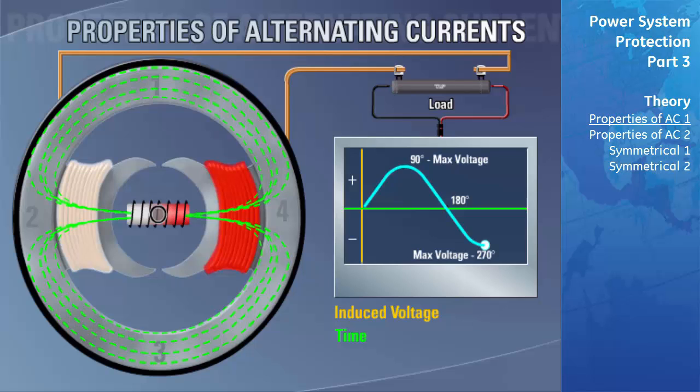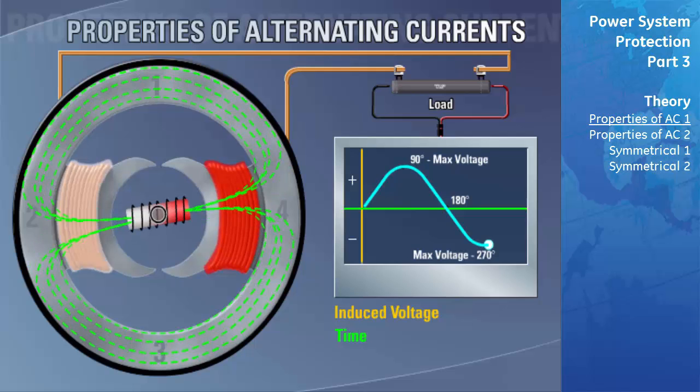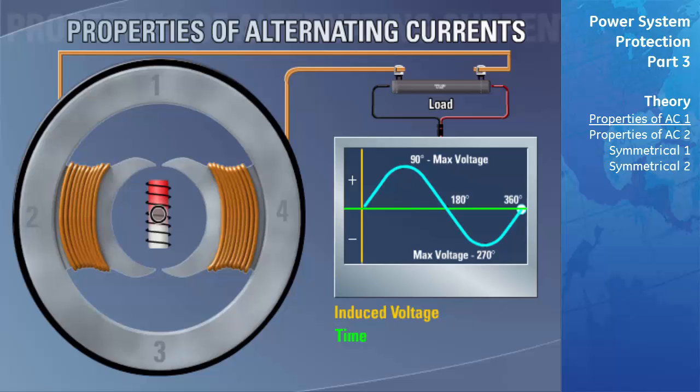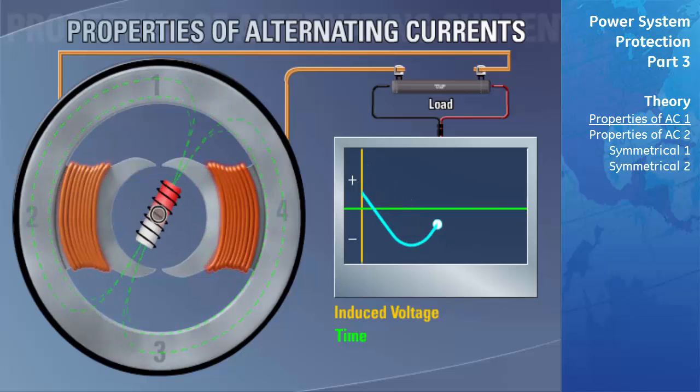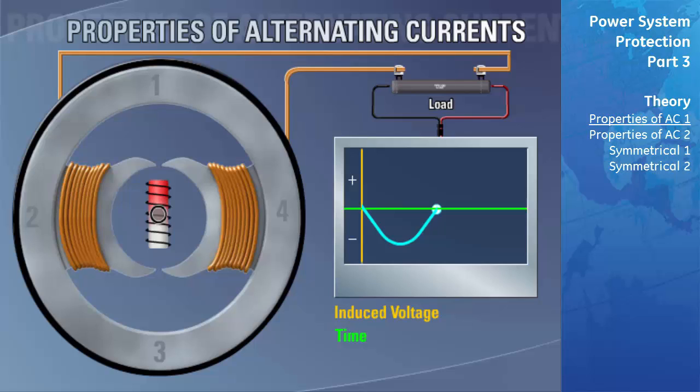As the exciter continues to rotate toward position four, the number of flux lines from the exciter's field flowing through the stator poles again increases, but because flux travels in the reverse direction, the induced voltage is of opposite polarity. The peak of this negative voltage corresponds to the north pole's alignment at position four. As the exciter rotates from position four back to position one, the induced voltage ramps from a maximum back to zero, completing one cycle of the waveform.